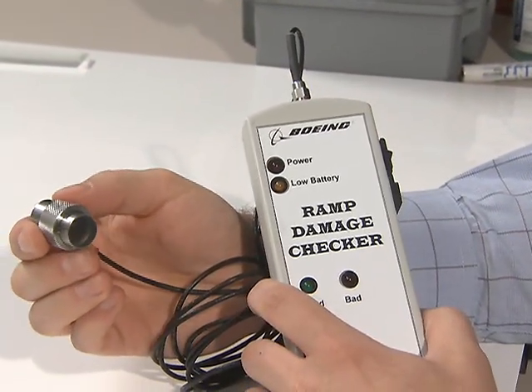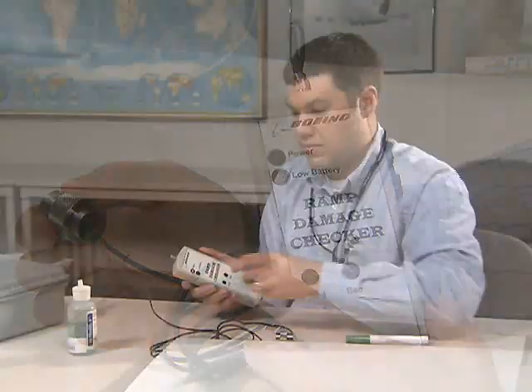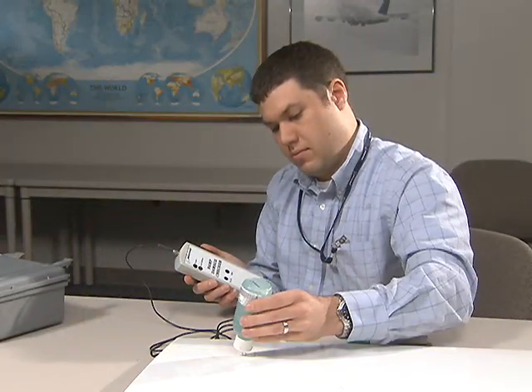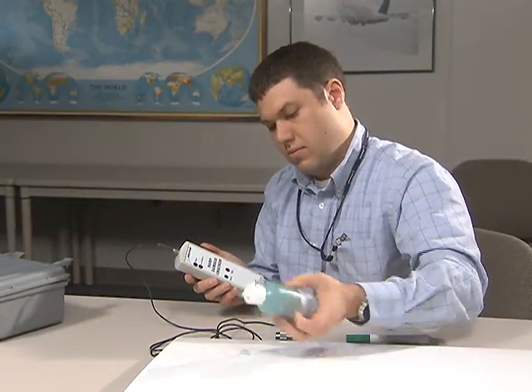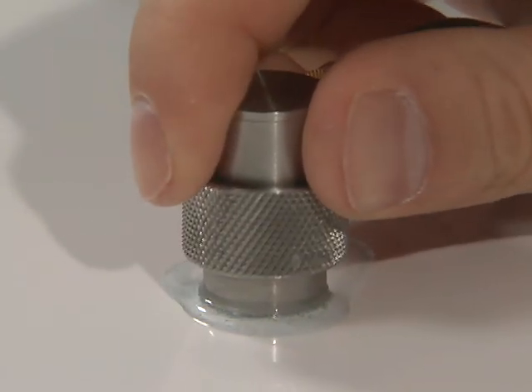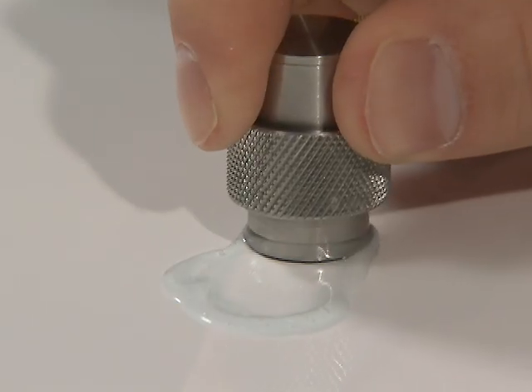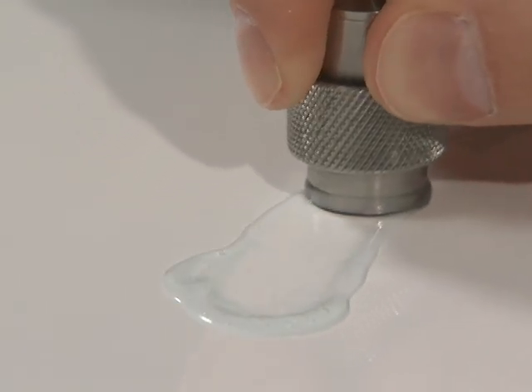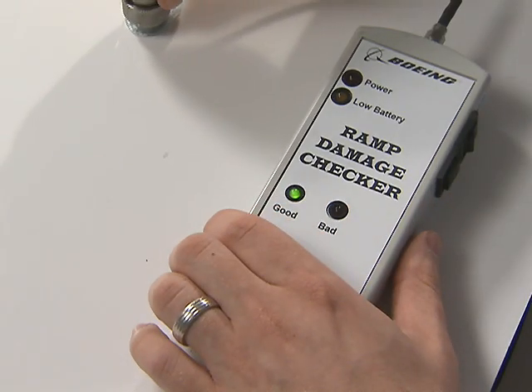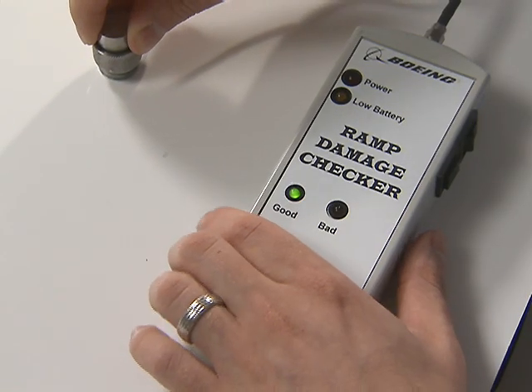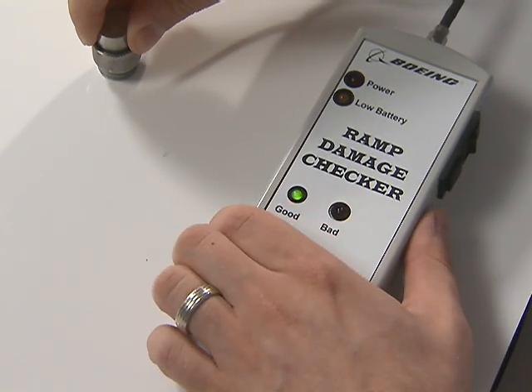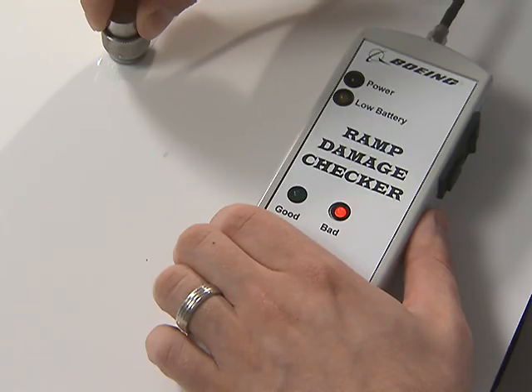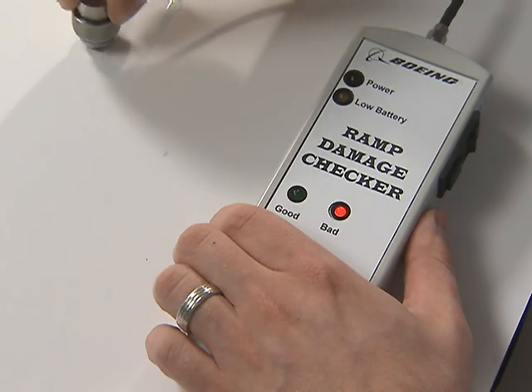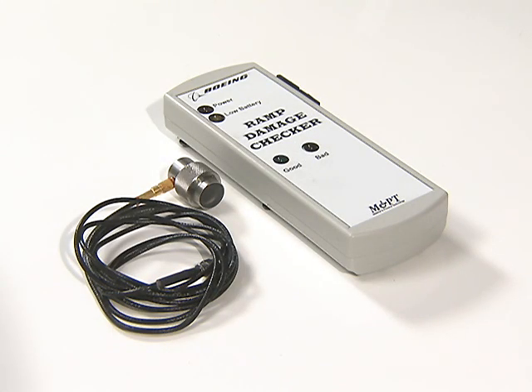Because the RDC is a simplified piece of equipment, it is possible to get incorrect data. You must have the proper training to use the RDC. The RDC compares the ultrasonic signal of the current probe location to the signal at calibration. Because the result depends not only on the defect area, but on the calibration area as well, it is critical that the user understands how the RDC makes its decision. First, a little background on the RDC and how it functions.